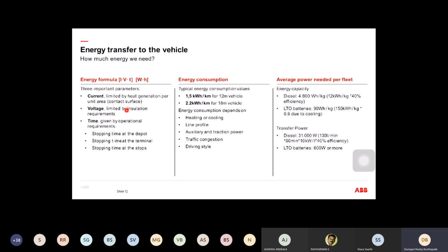When it comes to more than 1 kV, there are high standards which are difficult to meet. So generally e-buses are limited to less than 1000. So if it is less than 1000, why not 900 volts? There is a reason. Even in transients you should not cross 1 kilovolt. So to be on the safer side, generally they limit to a 500 or 600 volt DC bus. However, the battery voltage may vary from 900 to 200, depending on battery chemistry. That is on board, so they have their own requirements and will handle them.